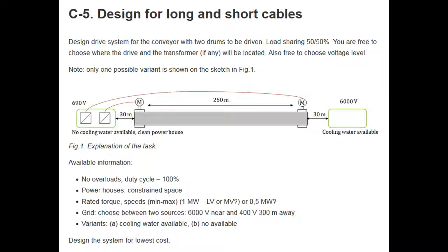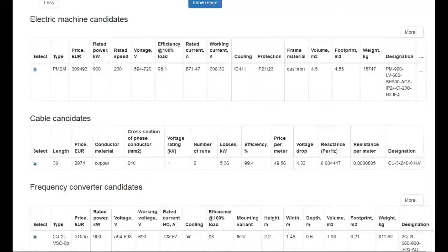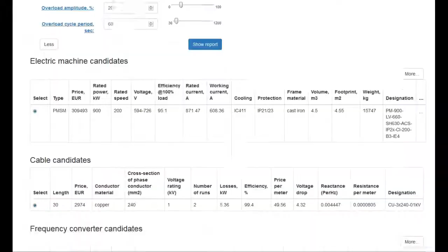First we set up all the parameters, and we know that the rated torque is just half of the overall rated torque, because we drive only one drum with one motor. So this is correct. And we see the motors and the converters are there, everything is chosen. Just note that the cable length is just 30 meters, and it's 99% efficiency in the cable.